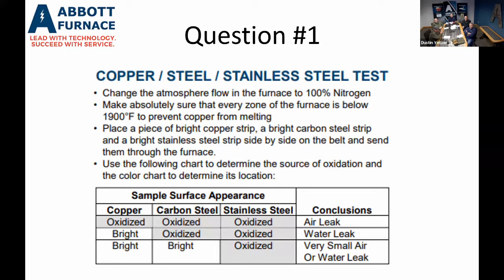I won't read it word for word, but you go to 100% nitrogen, 1900 degrees, and you're going to put a piece of copper, carbon, and stainless steel on it right through your belt. As you see at the bottom of that right there, depending on what's oxidized, what's bright, it will try to tell us what's going on inside that furnace as well. They do happen to work very well once that test comes out. I mean, if you've got an air leak, that'd be different. If you've got a water leak, then we'll go through and start checking dew points and different things we can do to figure out where that source of water is coming from.